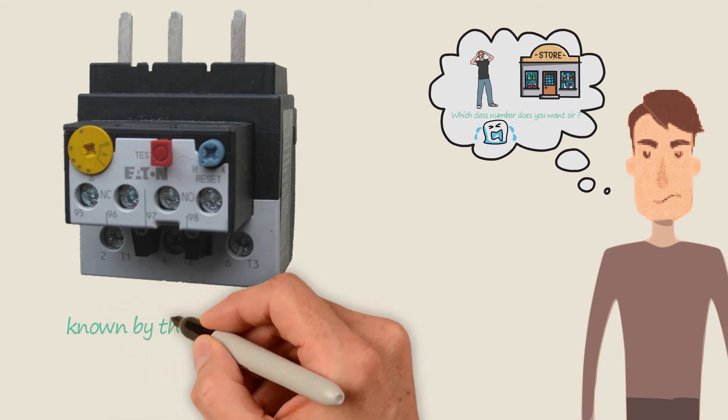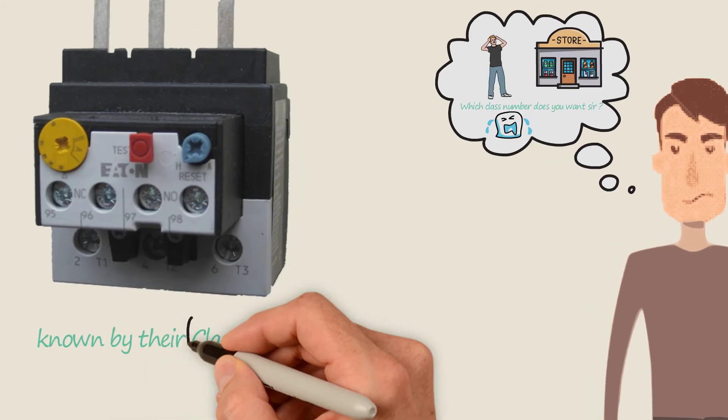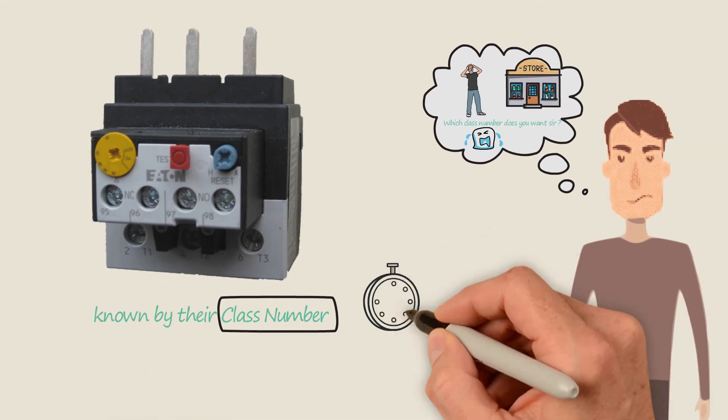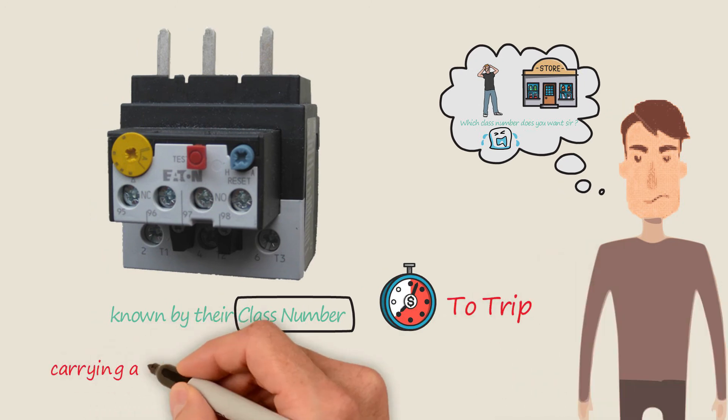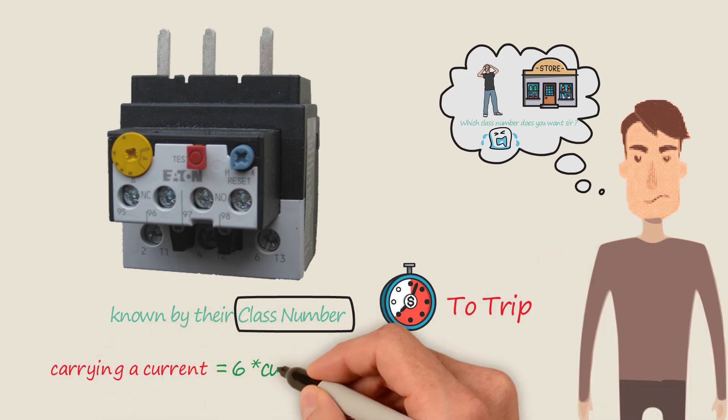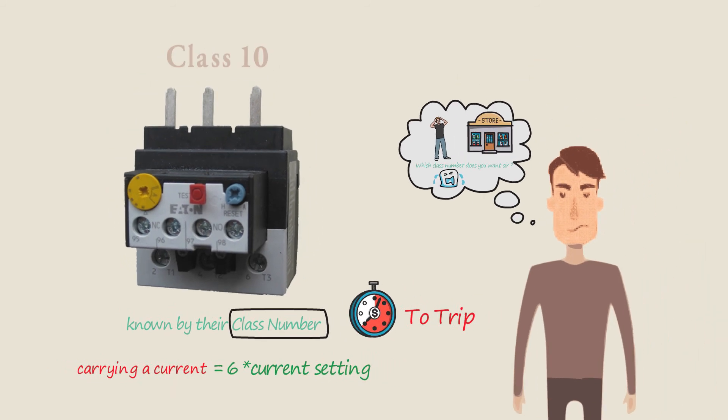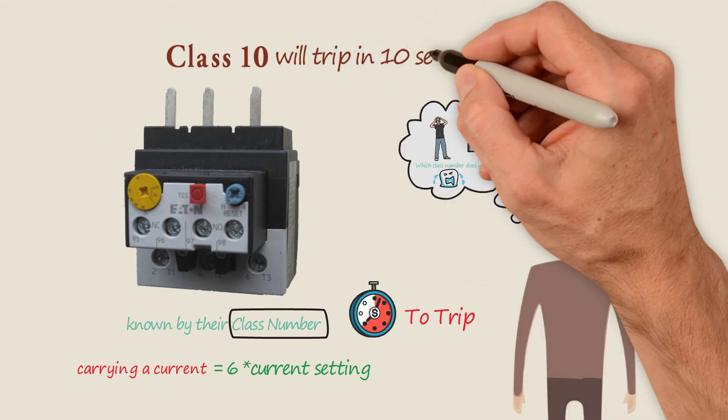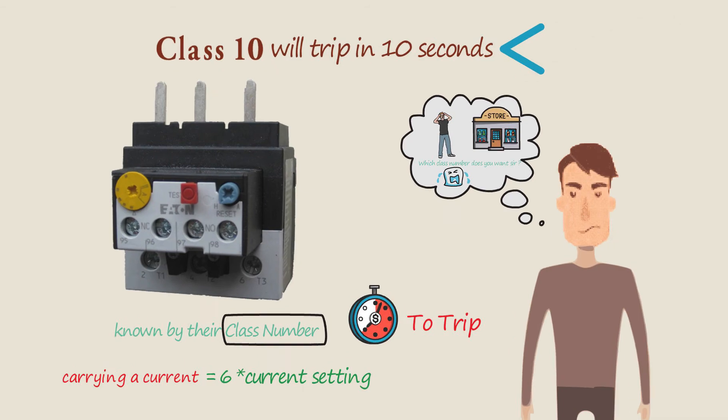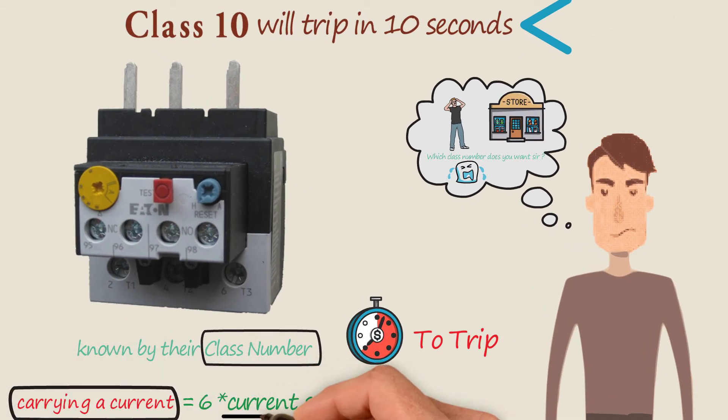Okay, overloads are known by their class number. The class number indicates how long an overload takes to trip when carrying a current equal to six times its current setting. A Class 10 relay will trip in 10 seconds or less when carrying a current equal to six times its rating.